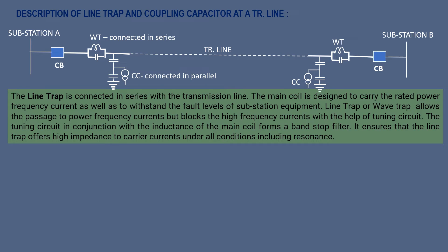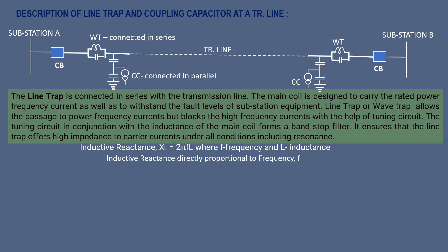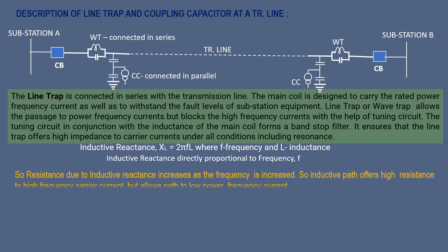The tuning circuit in conjunction with the inductance of the main coil forms a band-stop filter. It ensures that the line trap offers high impedance to carrier currents under all conditions including resonance. Inductive reactance XL = 2πfL, where f is frequency and L is inductance, so inductive reactance is directly proportional to frequency. Resistance due to inductive reactance increases as frequency increases, so the inductive path offers high resistance to high frequency carrier current but allows passage to low frequency current.